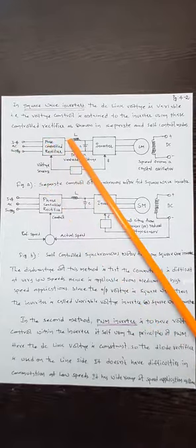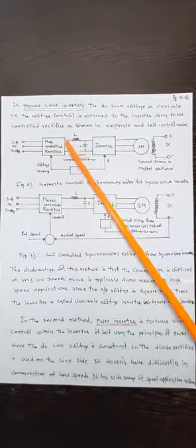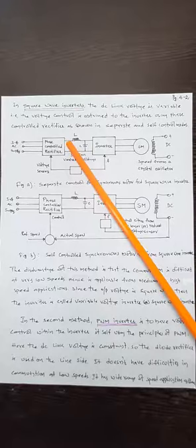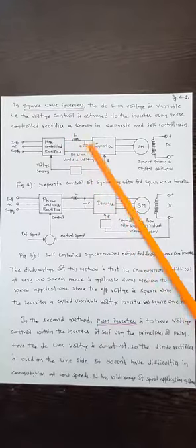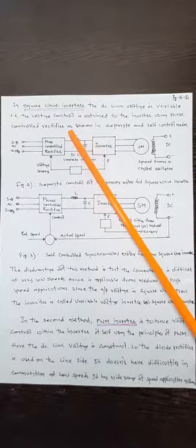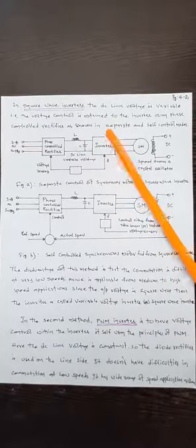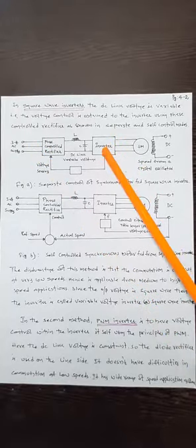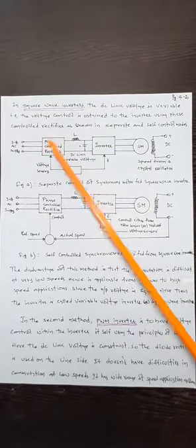So what it does, the three phase AC supply is converted into DC voltage. The DC output voltage is fed through a filter for improving the waveform, and that is again fed to the inverter. So the inverter has an ability to change the frequency. Variable voltage is coming from here, and by changing the firing angle of this converter, and frequency is obtained by changing the time period of the inverter, the timing sequence of the inverter switches.